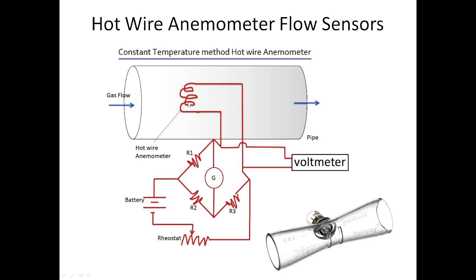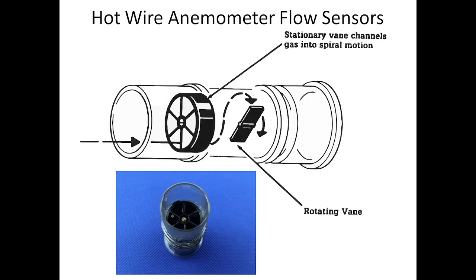Now this type of flow sensor is being monitored with a voltmeter, and there's a little galvanometer right down here, and there's a known voltage source and a rheostat. All that takes place on a single circuit board for the Dräger specifically. However, these are also some of the most reliable flow sensors, oddly enough, because they're very, very accurate when it comes to the quantity of flow. And because they're not inhibited by moisture, that means they're applicable in a wide range, whereas some of the other ones, like even flapper ones, tend to have some sort of condensation buildup over time. Now let's move into some technologies that aren't that common.